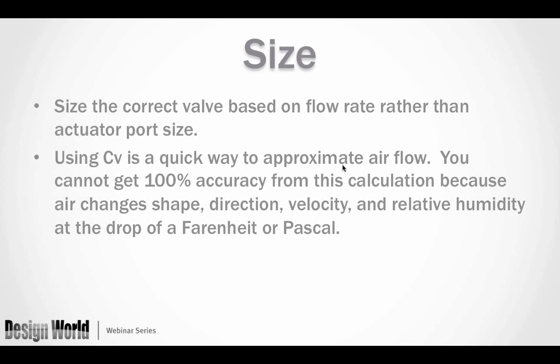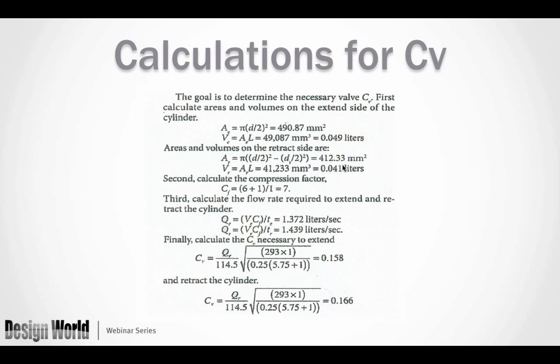Using C sub V (Cv) is a quick approximation for sizing a valve and a useful comparison between valves. However, Cv calculations are not 100% accurate because you need to know inlet and back pressures, temperatures, and other variables. Few people fully understand the Cv calculation formula, and fewer still go through the full calculation. The slide shows what you'd need to determine Cv for a valve or system to calculate flow — it's fairly complex and not something most people will work through in practice.